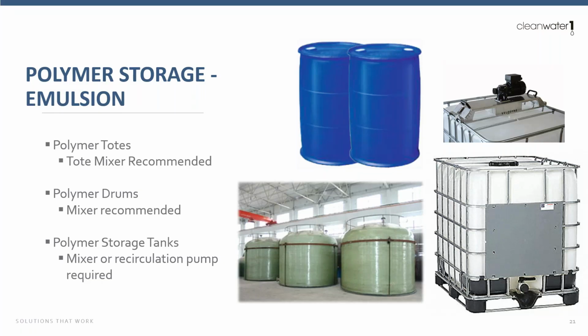With polymer storage tanks, we have a couple different options. We can use a tank mixer or we can use recirculation pumps. Both options can be used. With recirculation pumps, there are design considerations as well. We want the rate of that pump to be fast enough that we're actually mixing the tank. If we're pulling out of that tank at a low rate and putting it back in the tank, we're really just taking the polymer that was on the bottom and putting it right back on top. So we want to make sure that we're recirculating that tank fast enough to actually get that tank to mix. Depending on the tank size, for an 8,000 gallon bulk storage tank, generally that recirculation pump is going to be around a 50 gallon per minute pump.